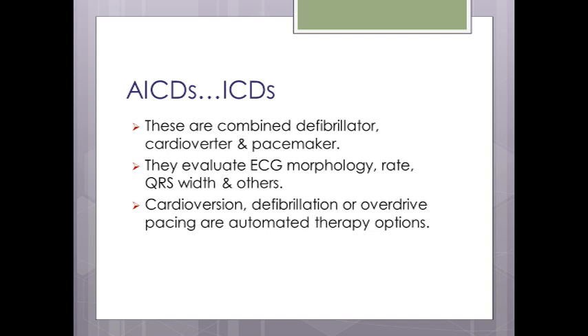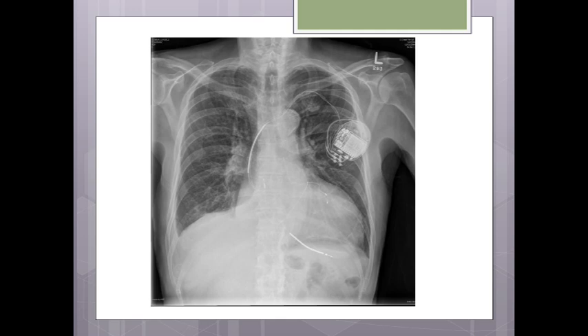Overdrive pacing works as follows: if a patient is in VT at 180 bpm, the pacemaker increases its pacing rate — for example to 250 bpm. Once capture is achieved, the re-entry focus generating the VT fires during the absolute refractory period of the pacemaker, effectively cutting the re-entry circuit. The pacemaker then gradually decreases its rate back to normal. This avoids delivering shocks — which are painful — and improves battery longevity.